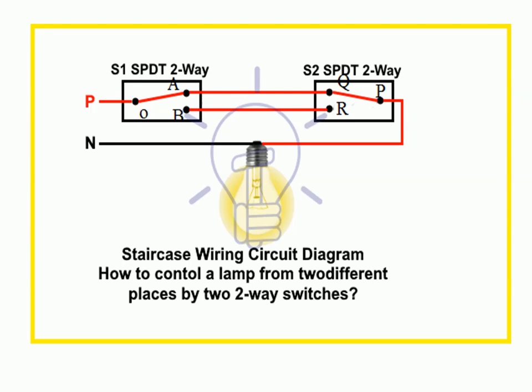Next one we can see there, two-way control. It is already known: one-way control means the operation of the lamp is controlled by one switch, a one-way switch. Now, the operation of the lamp is controlled by two switches. Two switches are placed at different places of the building. So, it is also referred to as staircase lighting, because one switch is placed at the ground floor, and another switch is placed on the first floor. Hence, we may control the operation of the lamp either from the ground floor or from the first floor. Hence, it is also referred to as staircase lighting, and it is known as two-way control of the lamp.